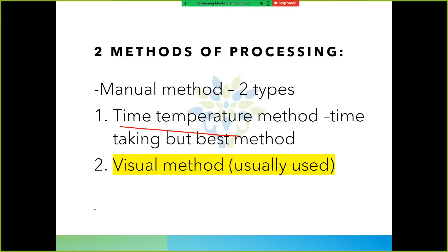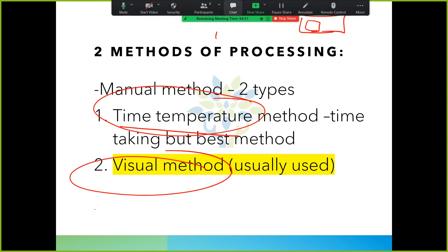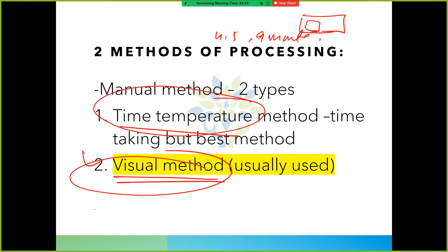There are two methods of processing. The time temperature method - which I was telling you - is the ideal method. And another one is the visual method, which we use generally. In the visual method, we put the x-ray film in the developer, and after some time we see it to check if it is developed or not. If it hasn't come well, we keep it again and check. Time temperature method is the ideal, but visual method is normally used.